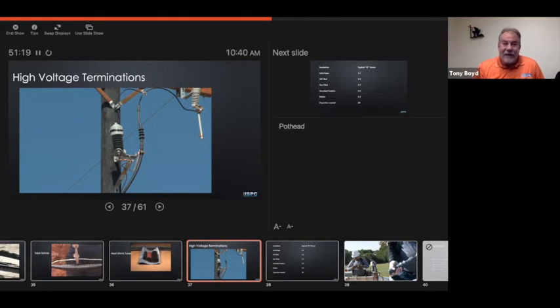So some things I want to show on this pothead: right here you see the concentric wire coming down, and it connects to the bottom of this lightning arrestor and then to the system neutral. Here the arrestor makes a tap onto the conductor coming up from the pothead into the bottom of the cutout. So this company puts an arrestor next to their underground system, and this is the pothead, although it's a lot smaller than the splice body or an elbow. It actually just does the same thing. The skirts allow for moisture and environmental conditions to go around and give more surface for that current leakage.